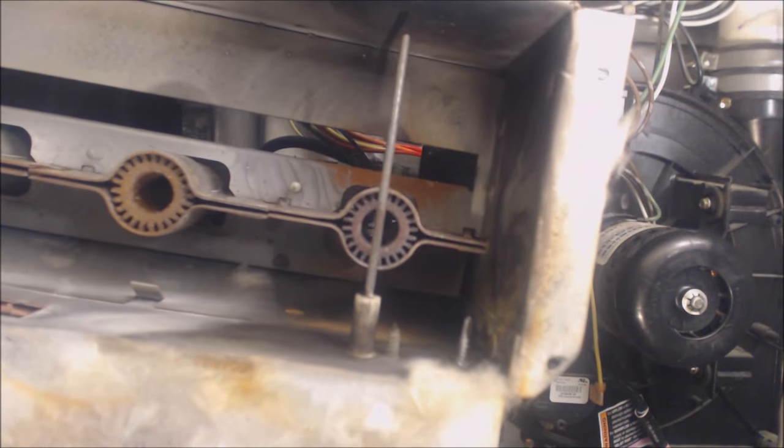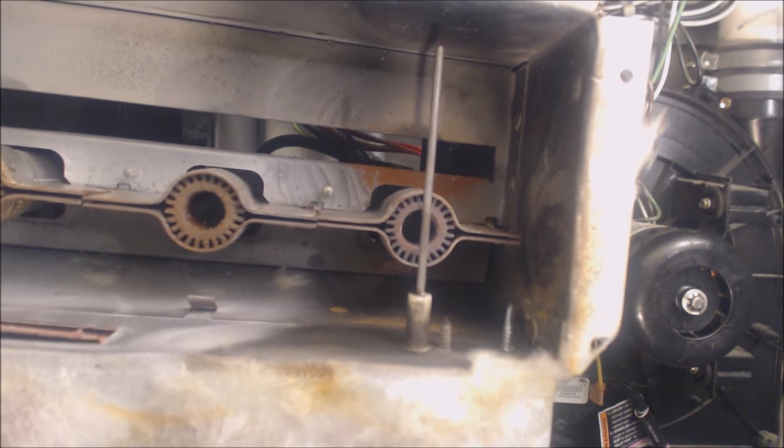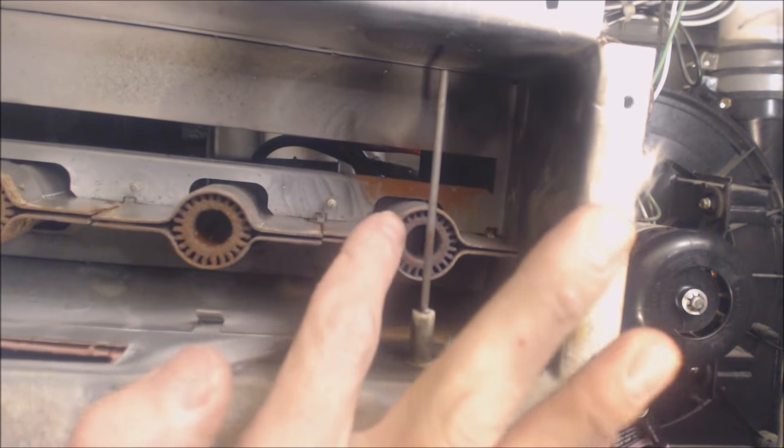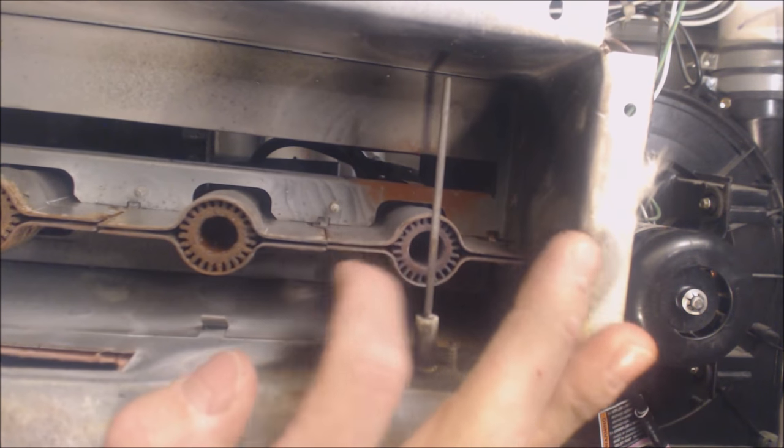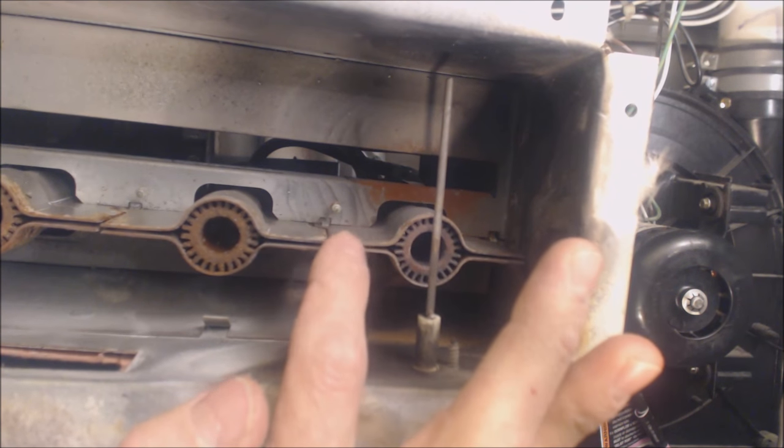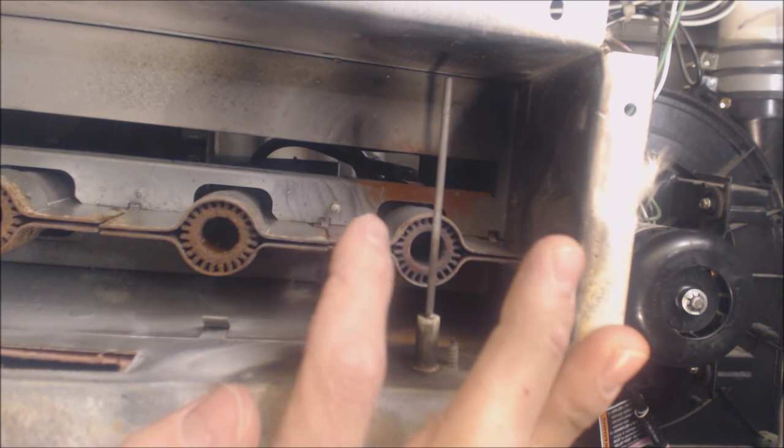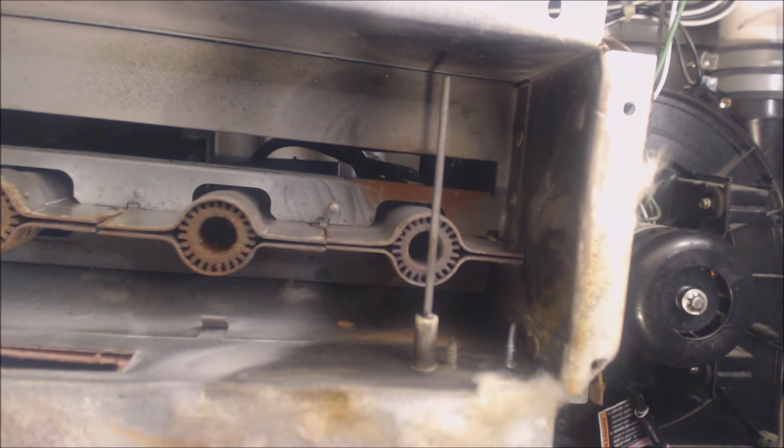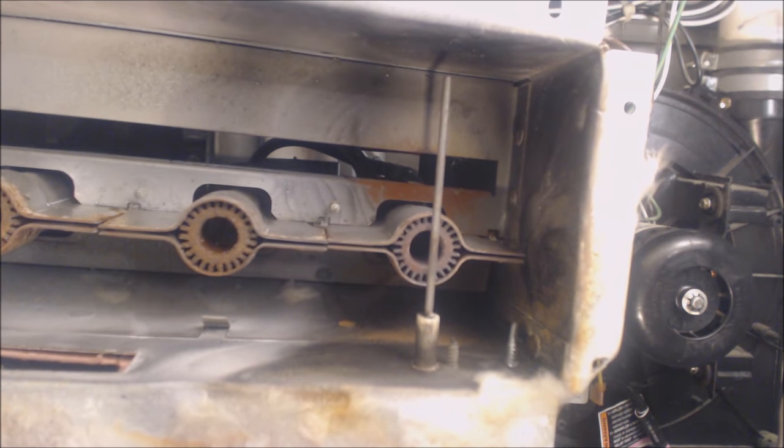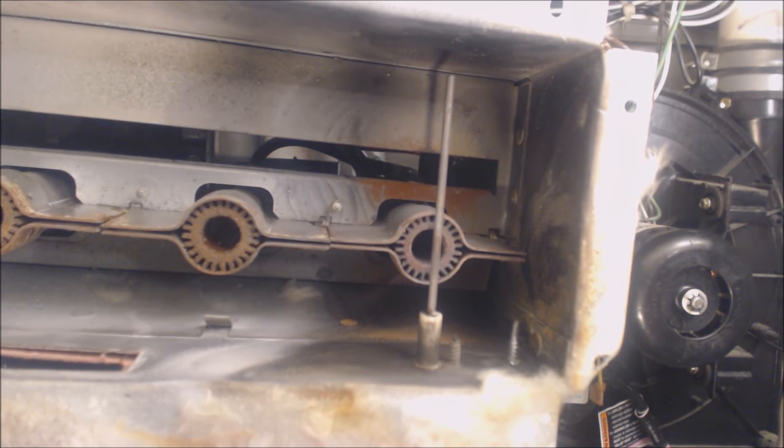But you just got to make sure that you have a good ground to your furnace and no potential voltage is on this ground. There's no potential voltage between the ground and the common circuit. That can mess up how the module reads that.